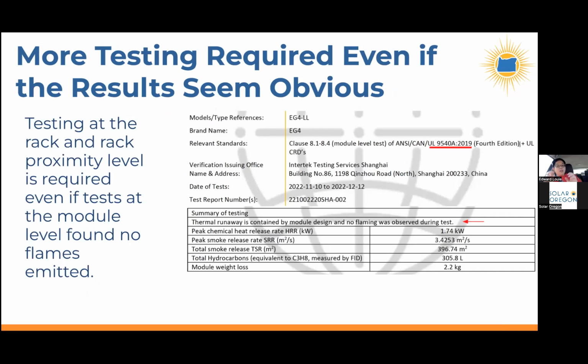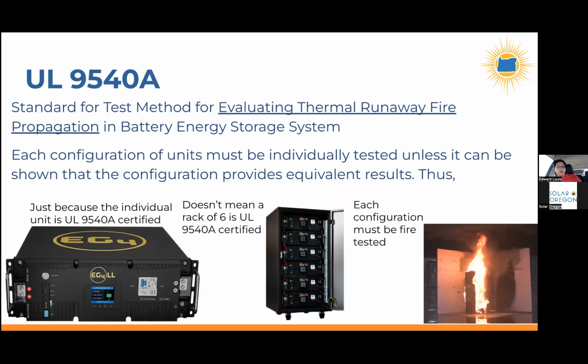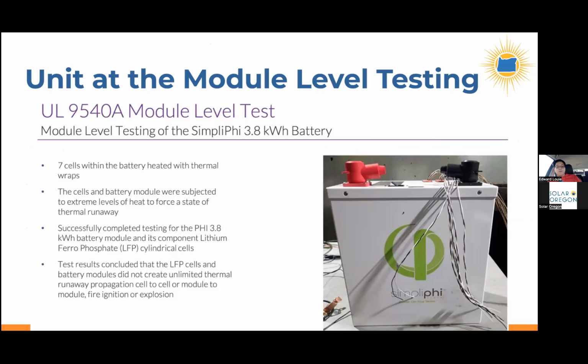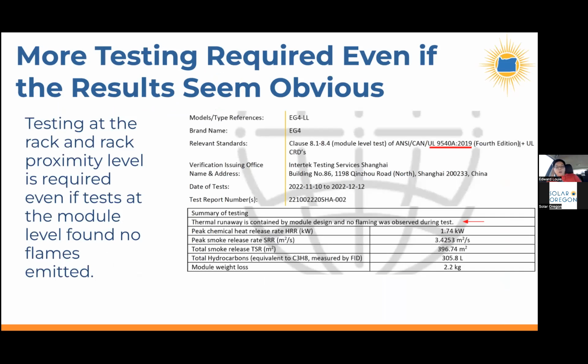And so these tests are required. So at the rack level, and then if you place the racks closer than 3 feet, you need to do another test. These tests are required, even if the test results will be fairly obvious from testing each, for example, rack mounted battery. So like here's an example. This server rack EG4LL battery, they did a UL 9540A test, and the summary of the test is thermal runaway is contained by module design and no flames was observed during the test. Okay, so no flame was observed during the test.